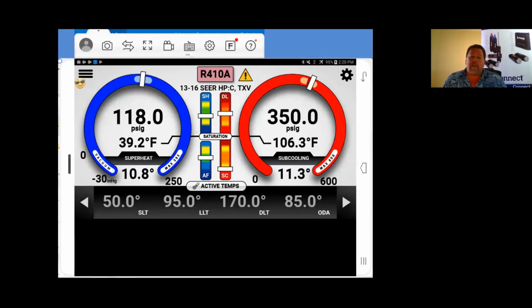But if you have insufficient compressor cooling, mostly that's going to be about probe placement. So take a look where you're placing your probes as far as your suction line, your liquid line temperatures. Take a look at that, because if your liquid line temperature probe is getting too close to the compressor, you're mainly leaning over towards discharge line temperature rather than liquid line temperature. It depends upon where you're picking up your suction line temperature, and depending if you have a receiver or not. Probe placement is everything. So keep an eye on your probe placement.